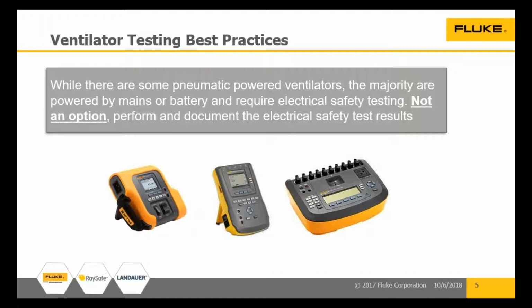But here's the voltages we're using: it's selectable, either 250 volts DC or 500 volts DC. So if the manufacturer doesn't specify the voltage to use, take your choice, document what you're going to do, and keep doing it.